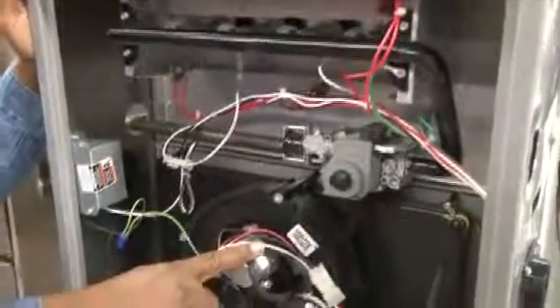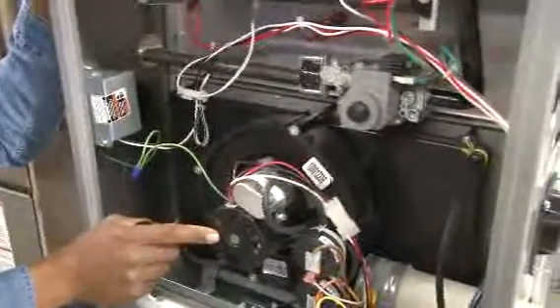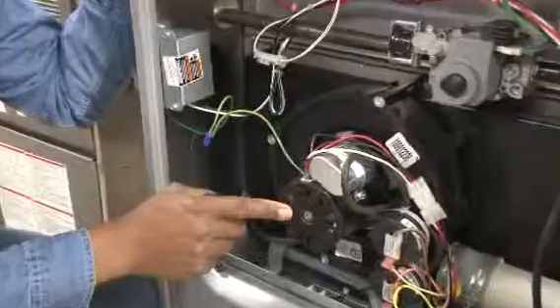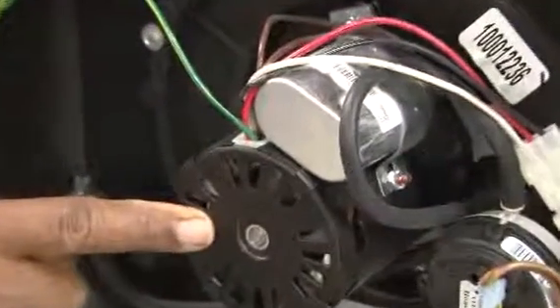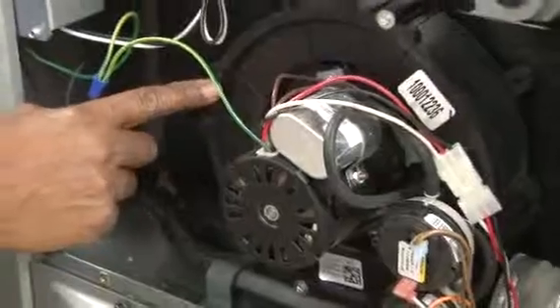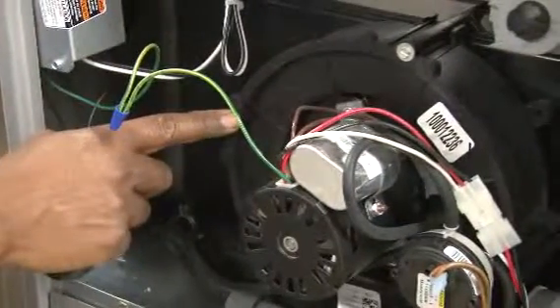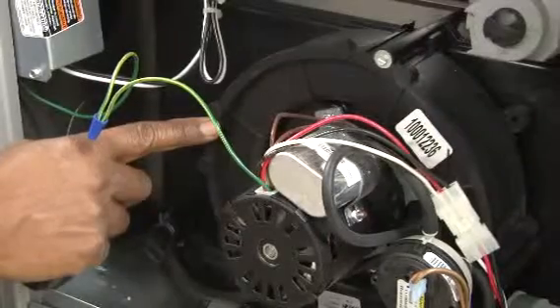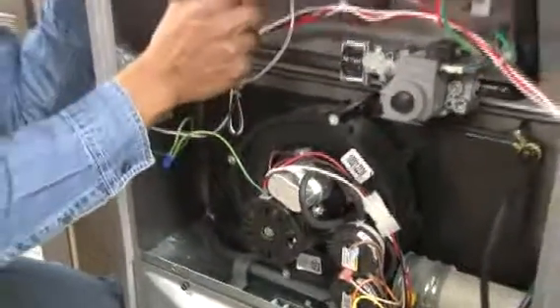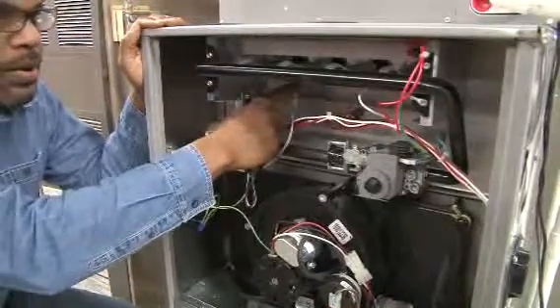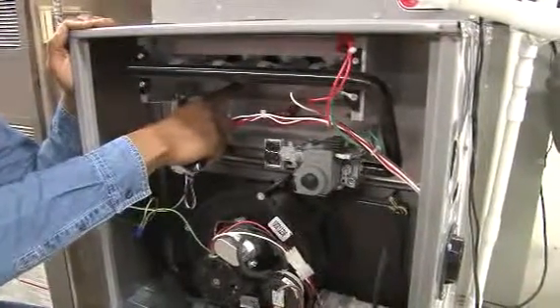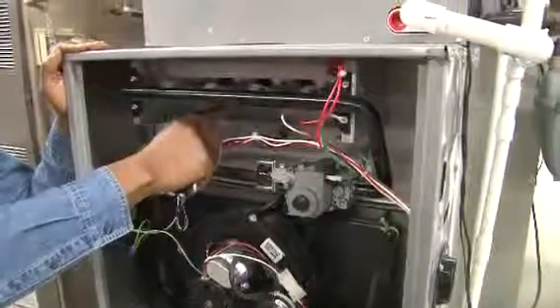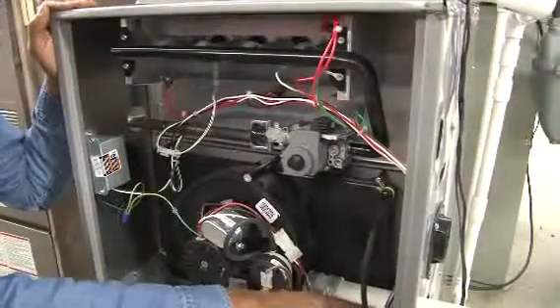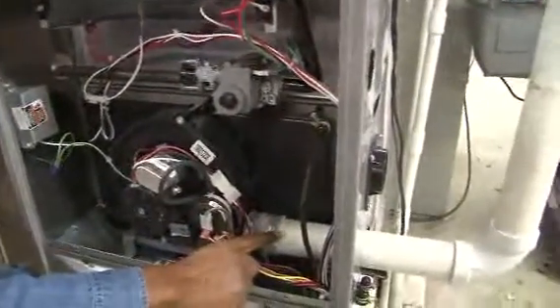The other component of it, because of the high efficiency of the furnace, is an induced draft motor. This induced draft motor is designed to force air into the heat exchanger to remove the flue gases. And what it does is, as it's pulling the flame in, it actually takes primary air, pulls it inside of the combustion chamber, and allows a draft to go through the heat exchanger, get collected inside of the blower, and exhausted out to outdoors through this PVC pipe.